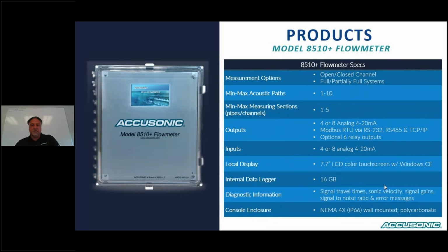We typically provide 6 relays as well, and each flow meter comes standard with Modbus, which can operate RS-232, 485, or TCP/IP. It is an LCD touchscreen display. It comes with an internal data logging function. It's user selectable as far as whether it's on or off, and the frequency, whether it's every 5 minutes, every minute, or even every second. A nice feature is that if there's a temporary test being done, the user can put a USB flash drive into the flow meter and temporarily log to that flash drive as well.